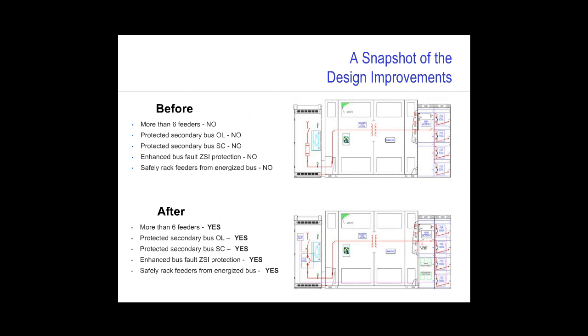So before we close out, let's take a quick snapshot of our before and after substation. Before, the workhorse of the industry involved a fused load break switch on the primary with no secondary main, and after, we actually have changed that fused load break switch to a switch and an integral vacuum circuit breaker, again with no secondary main. As you can see, the itemized list in the lower left gives us some advantages.